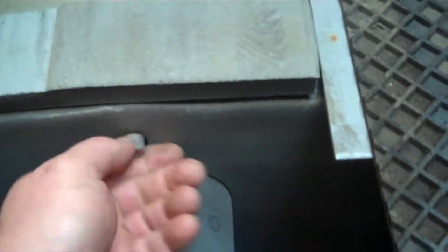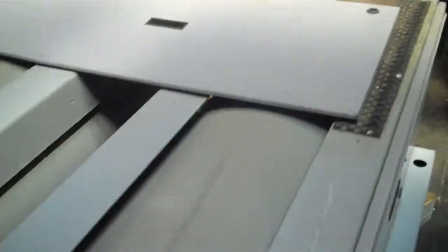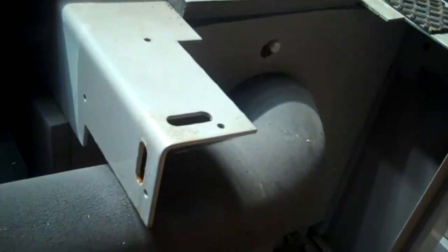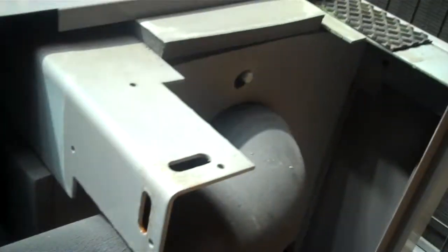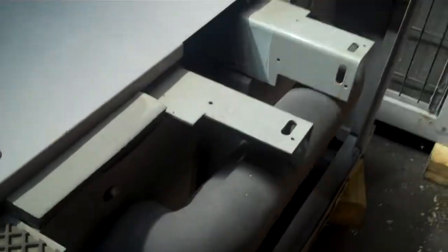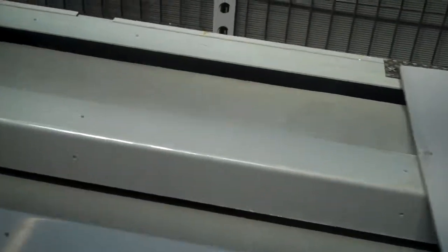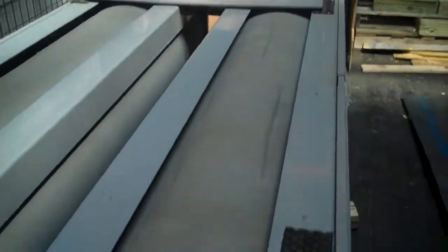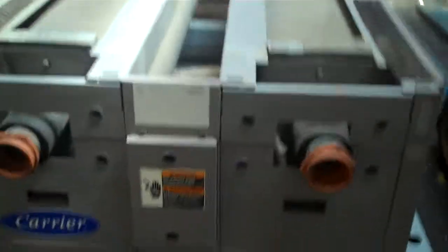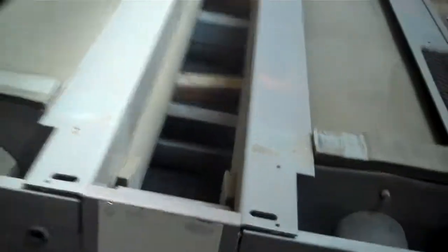Each end of the tank has a needle valve here to bleed any pressure out, and also each end of the tank, or tanks I should say, it totals 152 gallons. Has a drain plug also, and these two tanks are merely connected with that pipe right here. Now the tank piping is actually 3-inch. That's only so it can accommodate other sizes of chillers, but you're perfectly fine using 2-inch process piping for this. And if you want to, the tanks are also heated by a 230 volt single phase connection there.